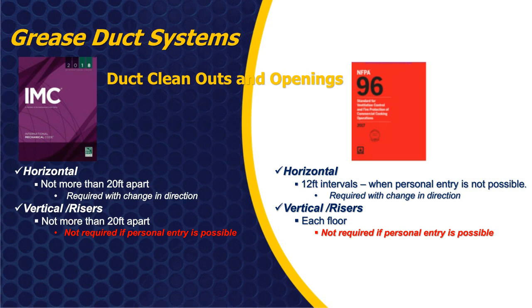If I bump over to NFPA 96, it's going to require the horizontal to have clean out accesses at 12-foot intervals, and required in changing directions. And then on the vertical riser, they're going to require them to have them on every single floor. Now, one note, they both say not required when personal entry is possible, and this is where I think it's really unclear. There's reference in there that a 20 by 20 square duct, or it could be 20-inch diameter round duct, would be considered accessible for personal entry, which, number one, people aren't getting these ducts used anyway. Number two is I doubt you get somebody to jump inside of a 20-inch diameter ductwork.